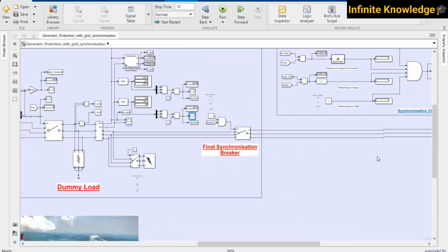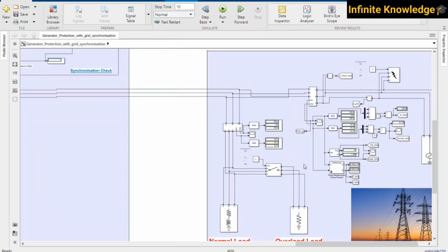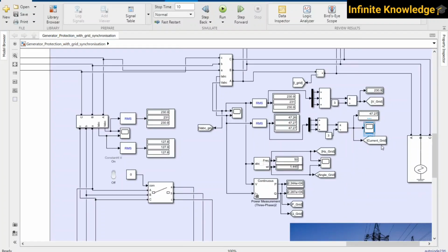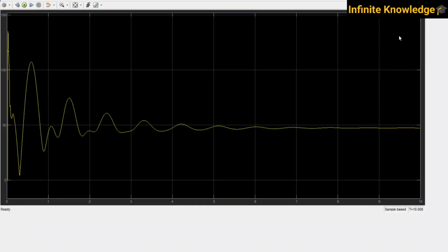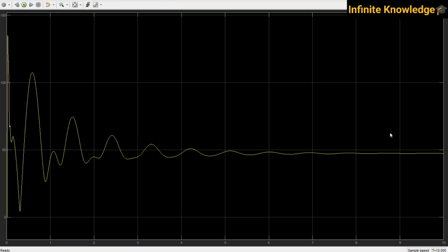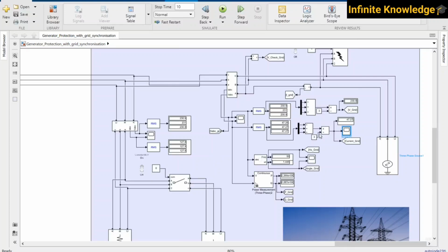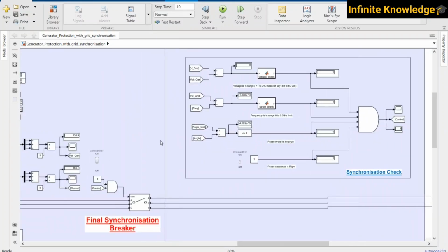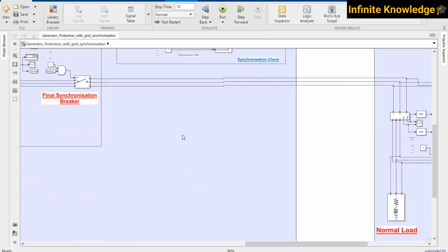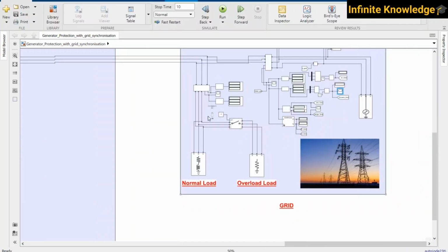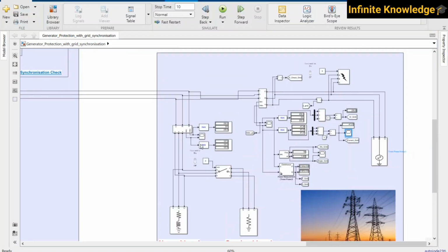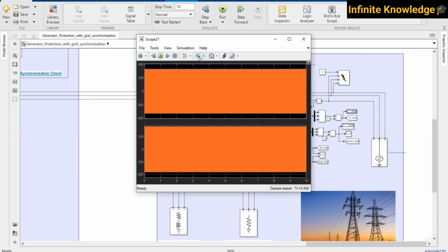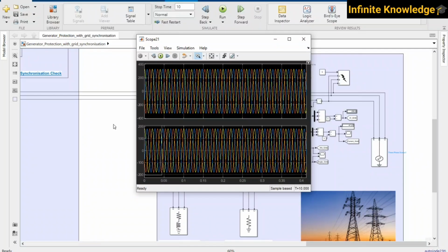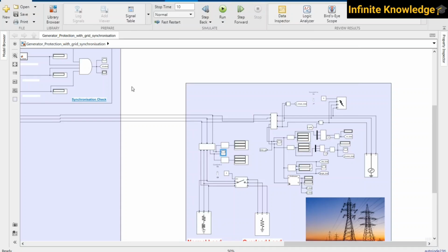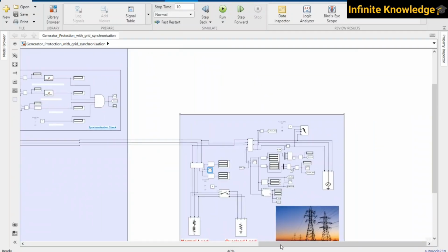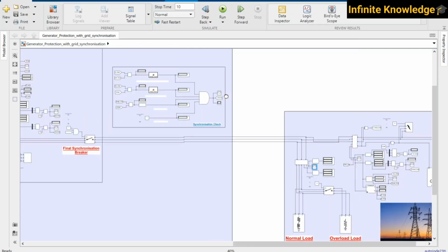And the same effect is on the grid side, because it affects the grid as well. If you want to check the current, you can see at this condition also a slight variation initially, and then it is totally stable. Okay, and 47 ampere is right now provided by the grid, and 165 ampere is taken by the load, and this is the final load taking this much energy. If you want to check the waveforms of the load, the current taken by the load is as per its requirement. The waveform is very clear, and there may be a slight current more than the load because of the circulating current between the grid and the generator.